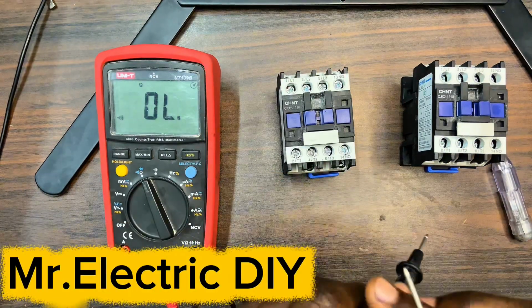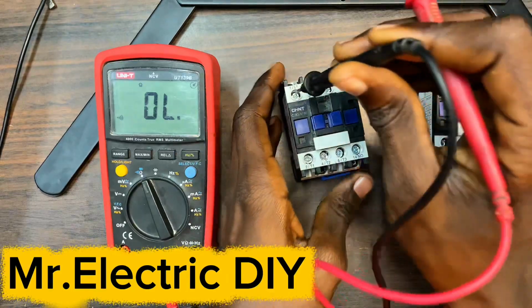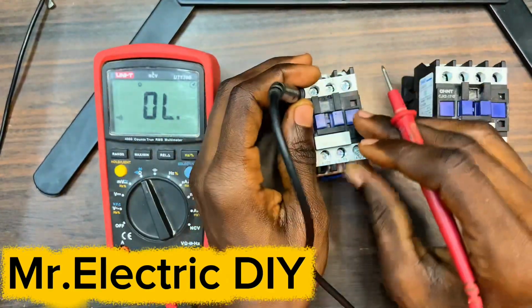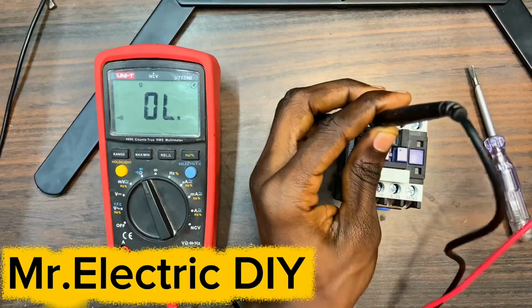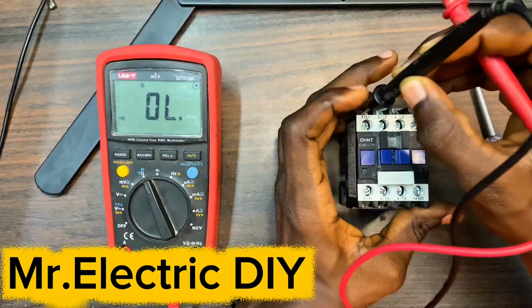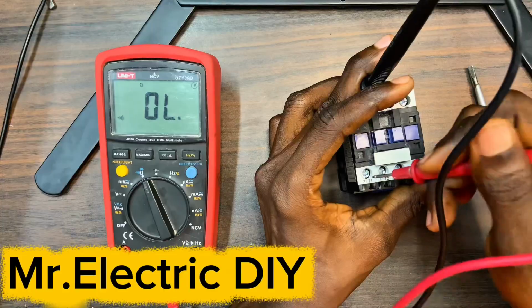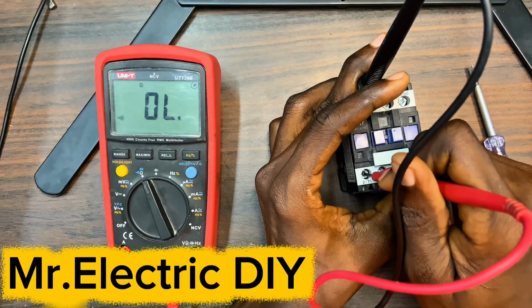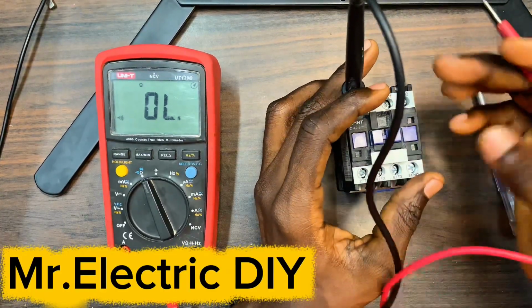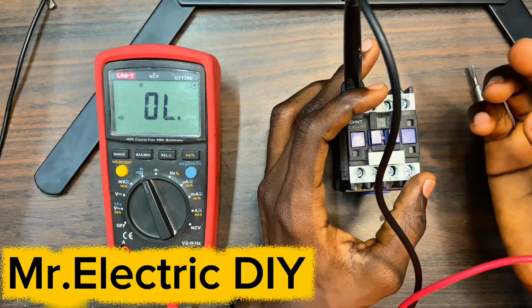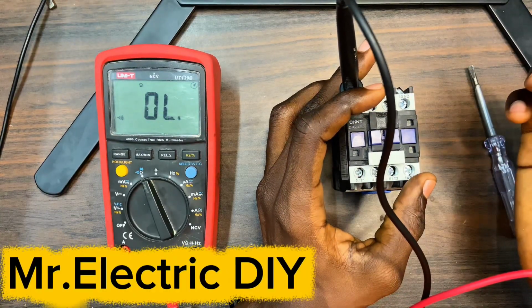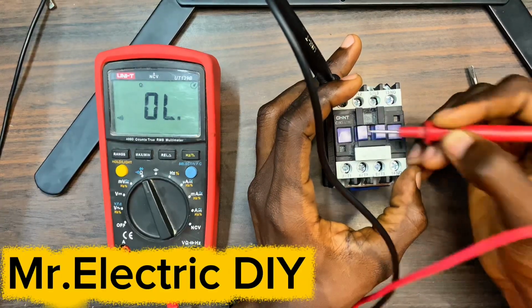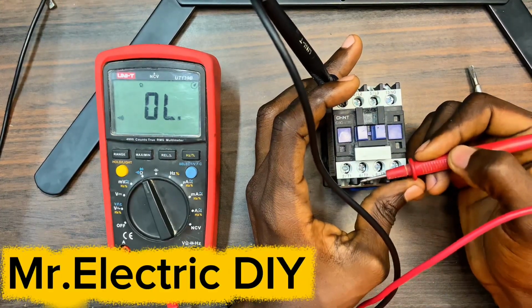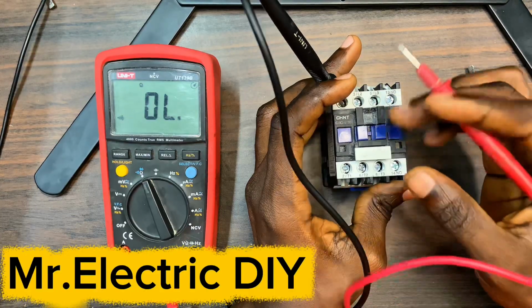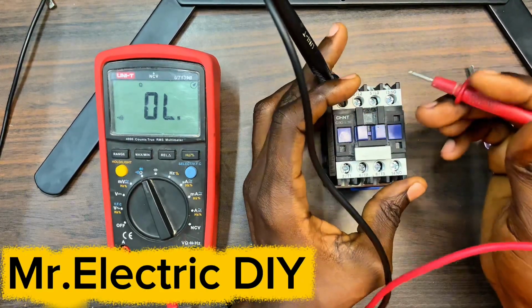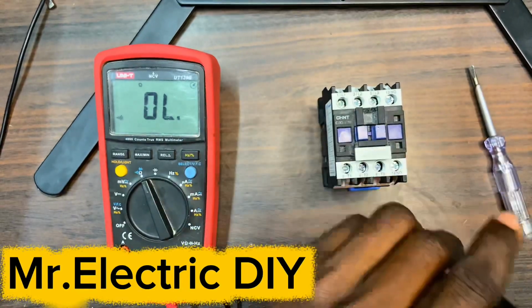Okay, so what I have to do is to connect one side of the probe to the input, and down here is the output. We are checking the reason why the motor is not receiving the right voltage or the 3-phase voltage. Contactor is energizing, but the output terminals, you are not having the 380 volts to the motor or to the load. So what you have to do is to check for continuity.